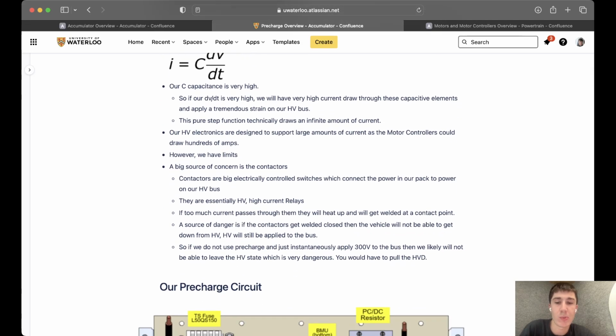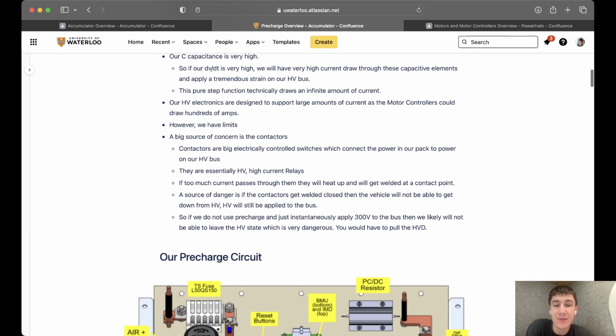A big source of concern when we're talking about high currents on our bus is our contactors. Contactors are essentially large electronically controlled switches which connect the power in our pack to our power on the HV bus. They are effectively high voltage, high current relays. If too much current passes through these contactors, they will heat up and the metal will actually melt and weld them, so if there's a lot of current going through the contactor, the connection point will weld and it will be impossible to open.